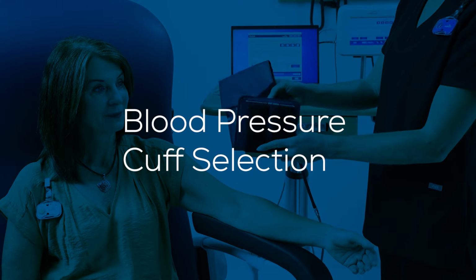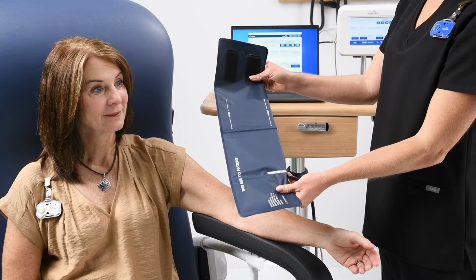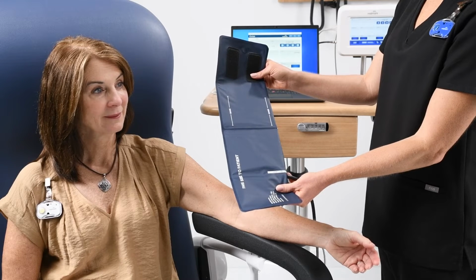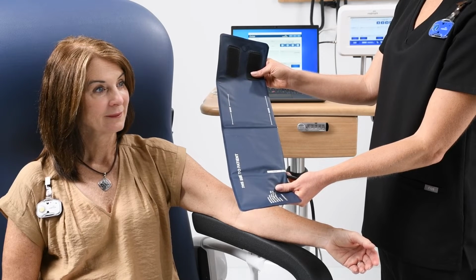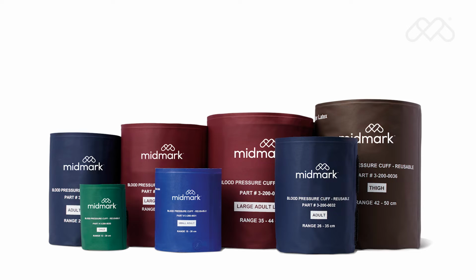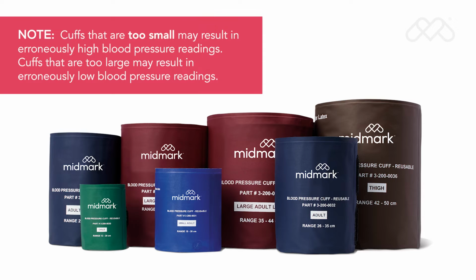Blood pressure cuff selection. Using the proper size blood pressure cuff is important for accurate blood pressure readings. Midmark recommends using Midmark or UltraCheck reusable cuffs with the Midmark Digital Vital Signs device. Cuffs that are too small may result in erroneously high blood pressure readings. Cuffs that are too large may result in erroneously low blood pressure readings.